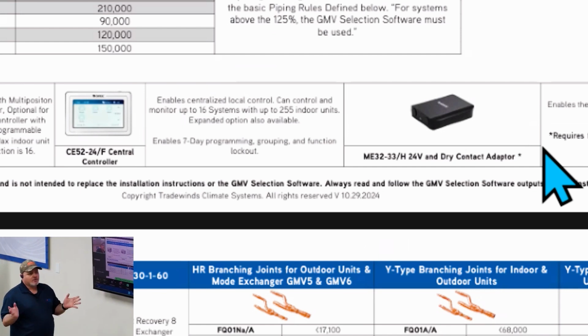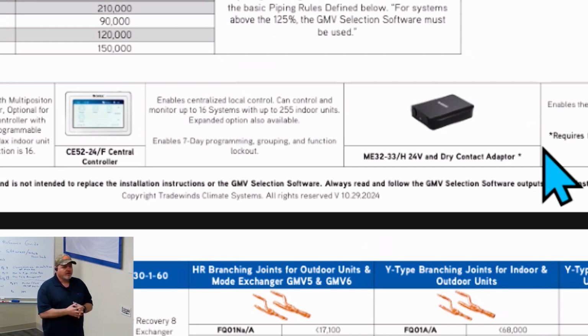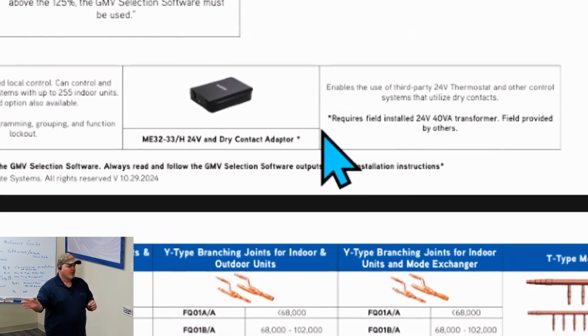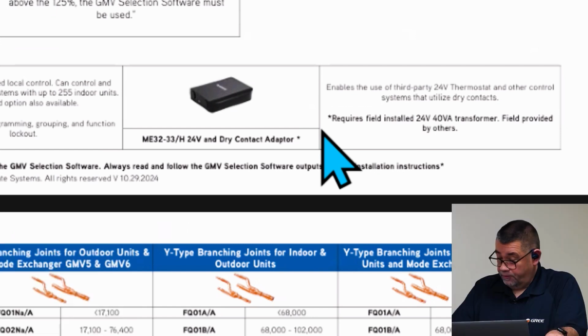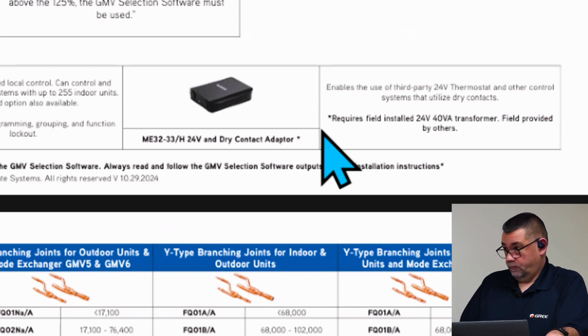All right, and then the 24-volt adapter is the last thing that we have to offer. That's for when the customer just does not like the GREE controller or the GREE remote. This gives you the ability on any of the indoor units to use whatever third-party thermostat you want, and it'll take that 24-volt signal and communicate to the communicating system and tell it what to do. The only thing with that 24-volt dry contact is you need to power it up with a 24-volt field-supplied transformer. Correct. Even on the air handlers, I'm going to point that out.